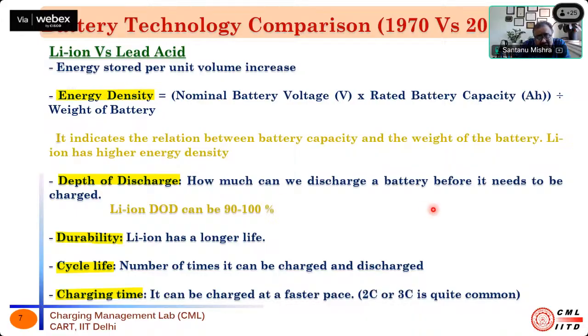Durability and long life are fine, but another very important thing that has happened with a lithium ion battery is that it has excellent charging time. The reason is that you can charge a lithium ion battery at 2C or 3C, meaning much higher than its own capacity. Like if a 30 kilowatt hour battery is there, if I charge it at 30 kilowatt, I'm charging at C, the capacity rate of the battery. I can also charge it at 60 kilowatt, which is 2C, or 90 kilowatt, which is 3C, and by doing that I am reducing the charging time.